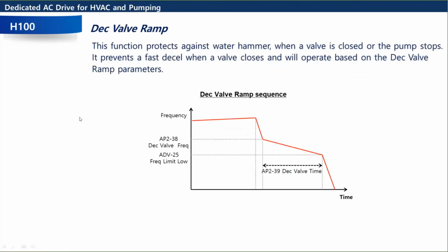We have a valve ramp. This is going to be used when you have a check valve. It's a way to prevent against water hammering. It's very similar to what we were just talking about, but it's a valve ramp for a check valve. It'll ramp down pretty quick, so you don't have any chattering or water hammering.